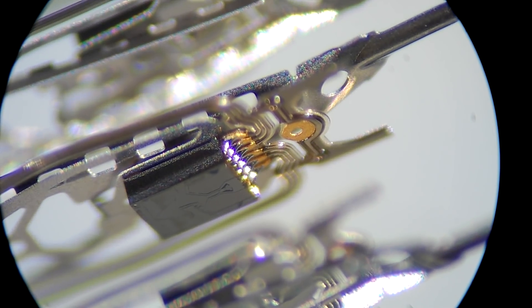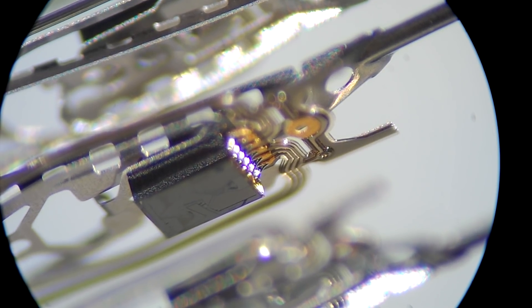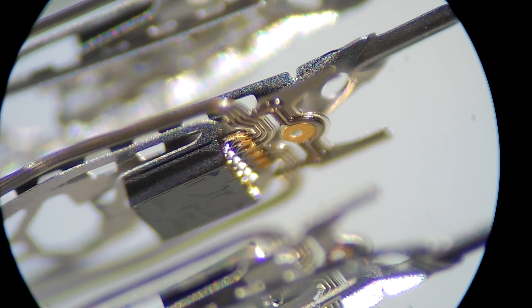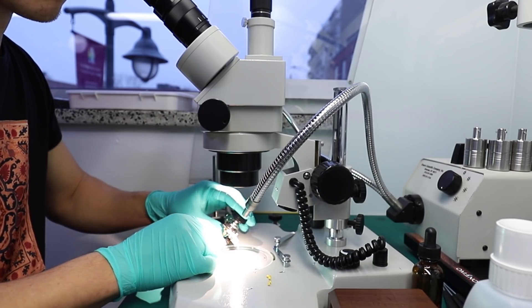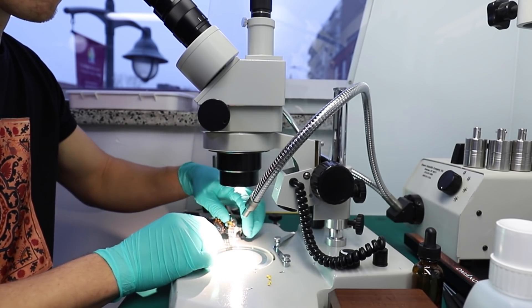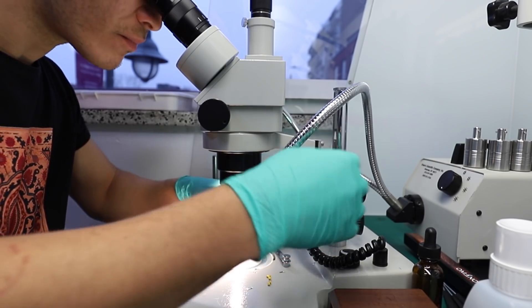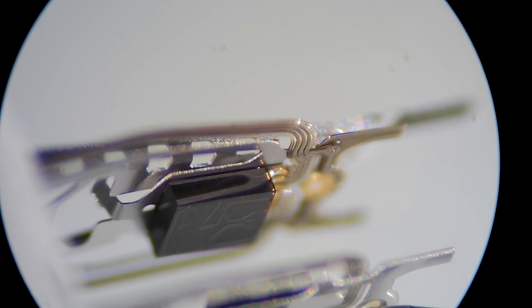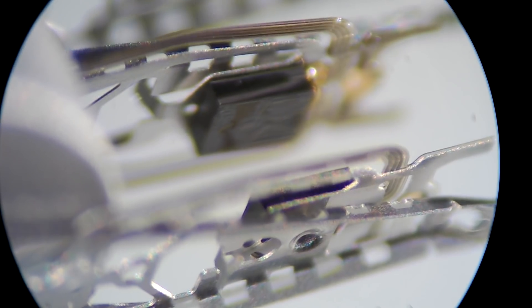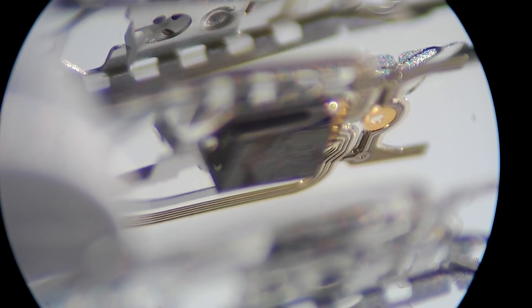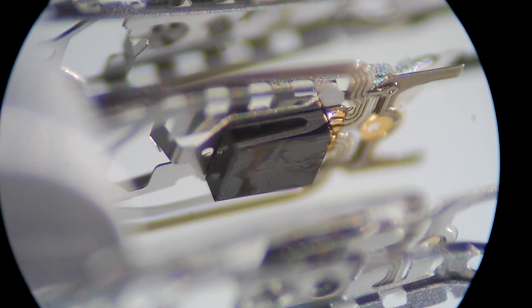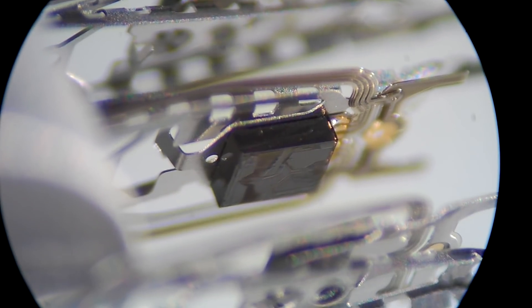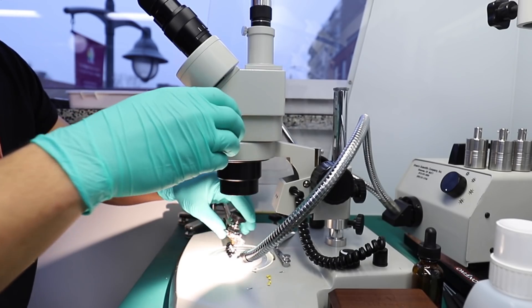Looking at this head assembly right now, we see that head zero is contaminated badly, but head number two wasn't as badly contaminated. In the head assembly, the sequence begins with zero, then one, then two, then three. The bottom disc carries head zero and one, the top disc carries head two and three. Right now you're looking at head one, and the lowest one that's turned away from us is head zero.